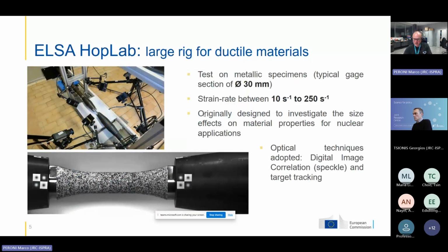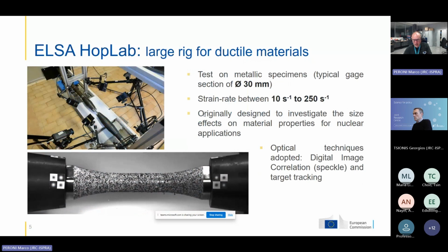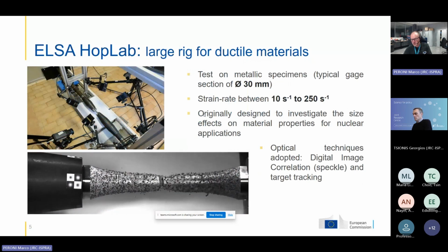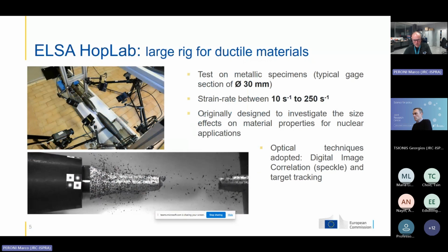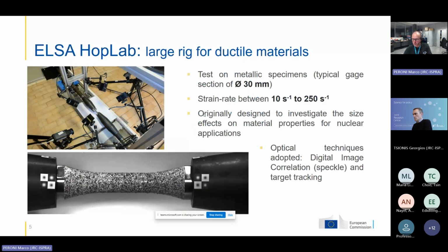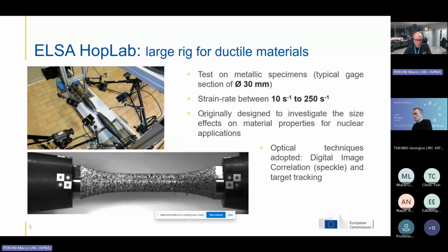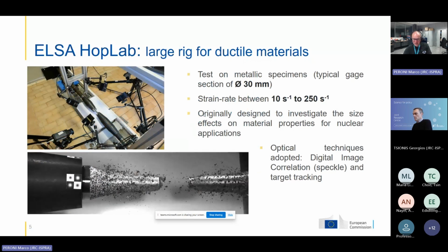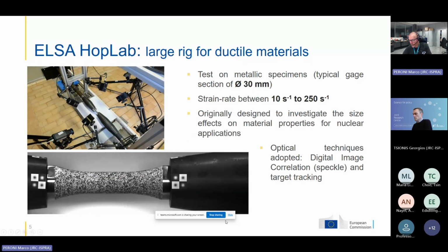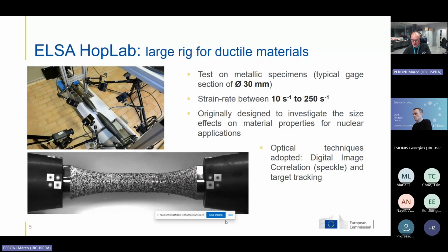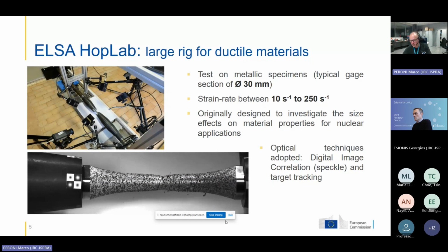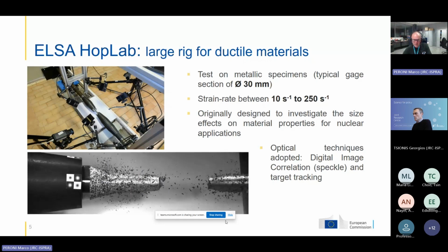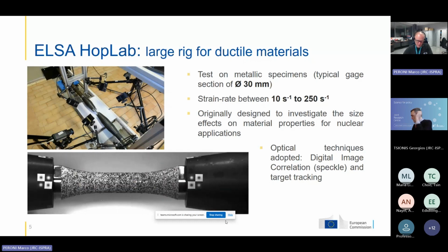In this kind of experiment, we typically adopt high-speed imaging, because it's not possible to see anything with your eye. The instrumentation is also quite complex and dedicated, because we have to acquire measurements up to 1 to 10 megahertz. The video at the bottom shows the classical specimen for metallic material that we use, which has a gauge cross-section up to 30 millimeters, and gives you an idea of our capability in terms of load and forces.